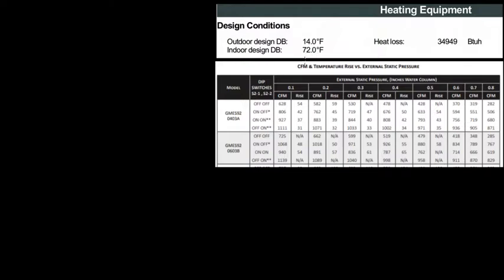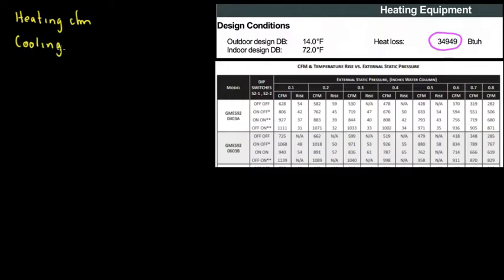To begin with, what we have is the heat load calculation. The heat load is 34,949 BTUs per hour. When we are sizing equipment for residential purposes, we actually have two CFMs: a heating CFM and a cooling CFM.